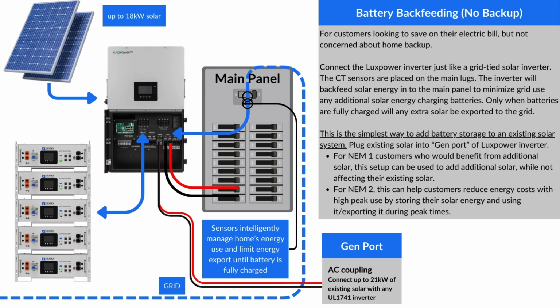But if the grid goes down, they're not concerned about it, or they have so infrequent grid outages that it's not a priority for them. And in this case, you're wiring the inverter very similar to a traditional grid-tied inverter, where grid lines are going to be coming from the main panel into the inverter, and there's really no circuits connected to the load output. And then by using the CT sensors on the main lugs in the main panel, the inverter will actively backfeed into the main panel to try to zero out what the home is using.